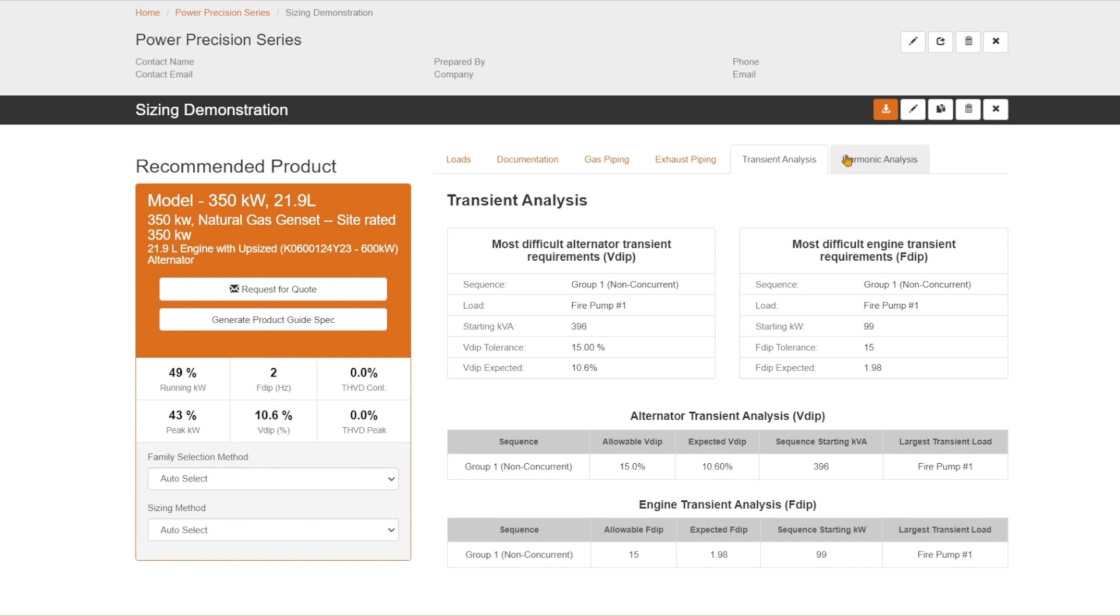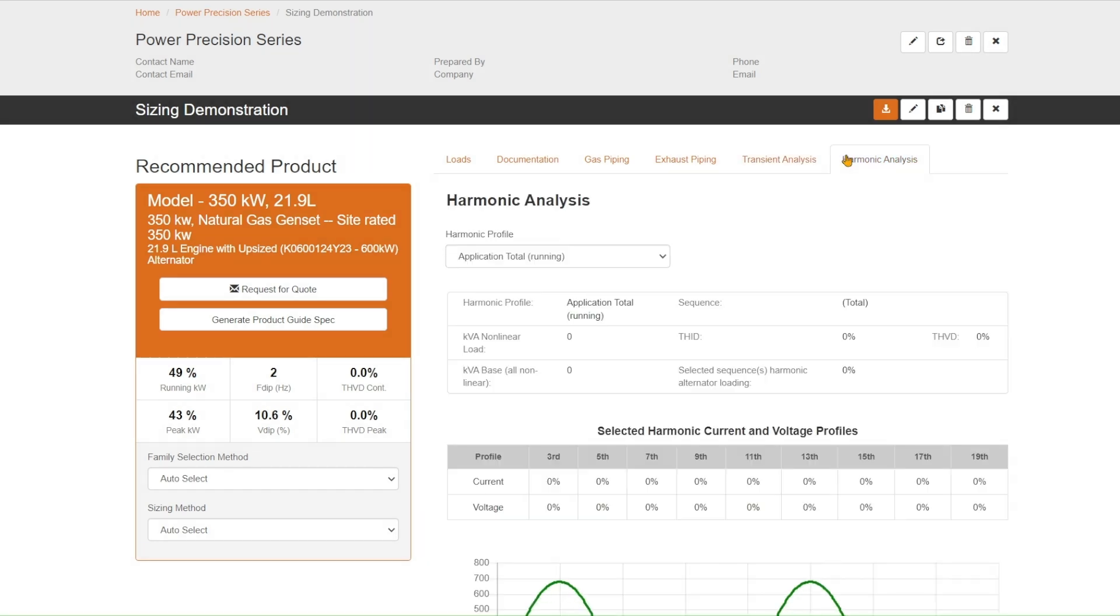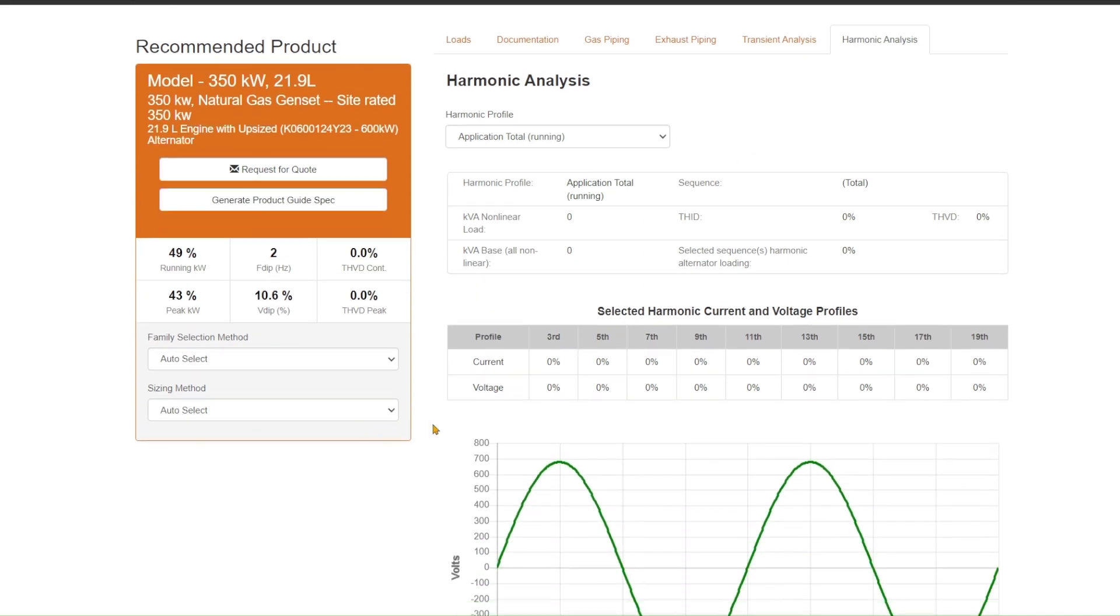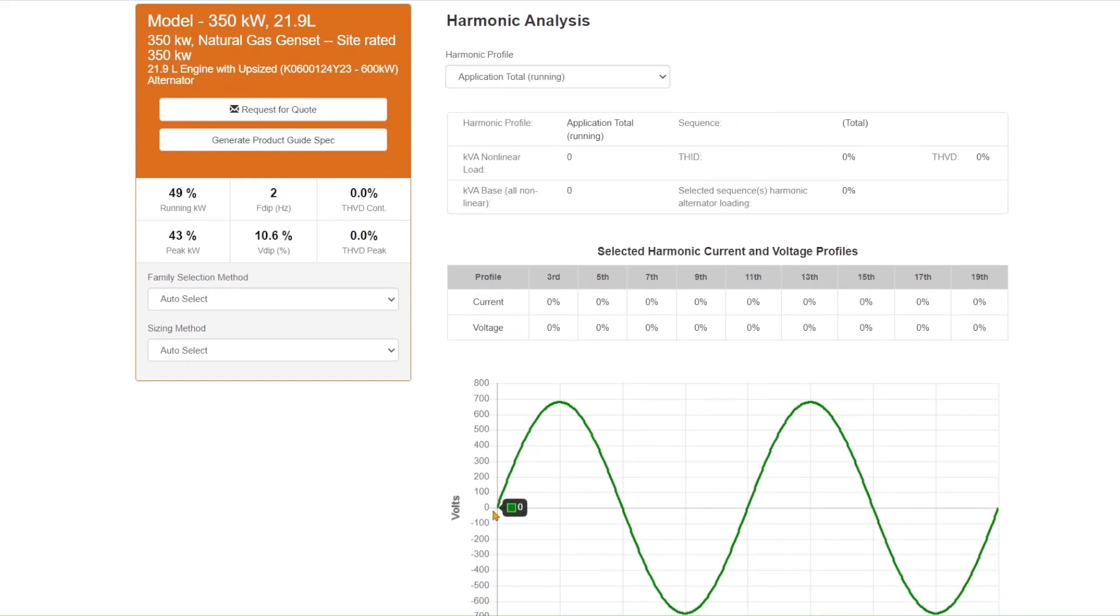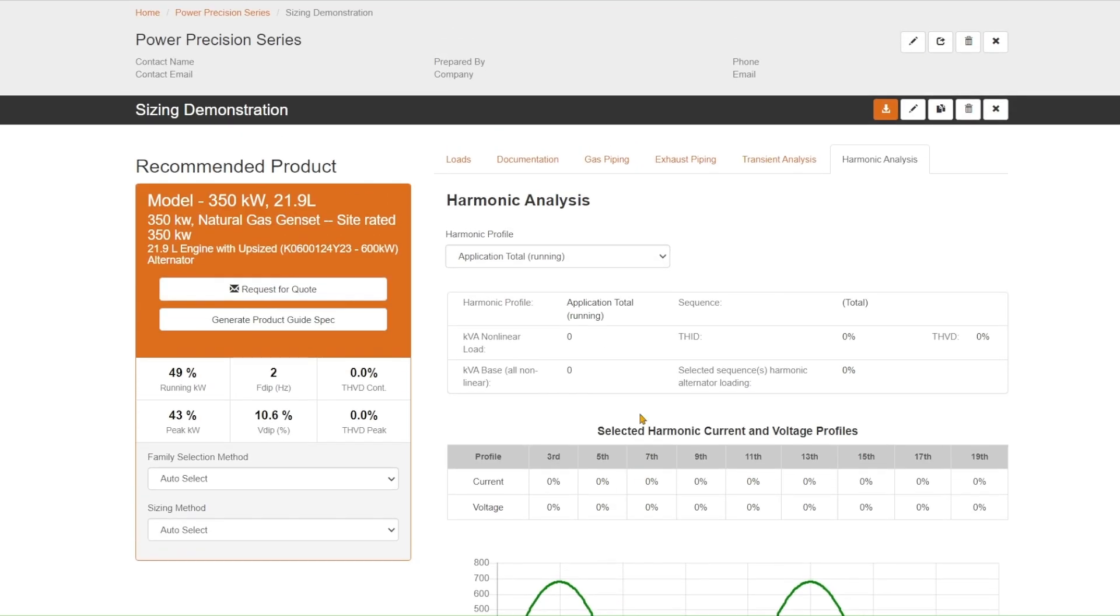Lastly, we have a tab on harmonic analysis. Harmonic analysis is just talking about non-linear loads and how they impact the generator. This particular solution, we didn't put any loads in there that were non-linear, so we have a nice smooth sine wave, not an issue there.